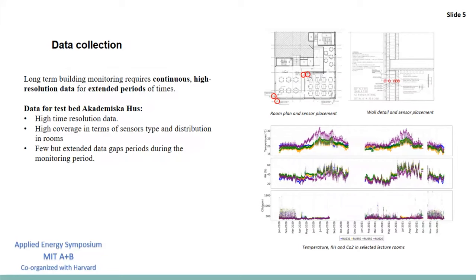Long-term building monitoring requires continuous high resolution data for extended periods of time. For this specific building the resolution of the data and coverage in terms of distribution is high. In the figure on the right hand side you can see the distribution within one of the floor plans and the construction details showing sensors embedded within the wall structure. The plot below shows hourly temperature, relative humidity and CO2 concentration during 2020 and 2021 in selected rooms. From the plots we can see that there are extended periods of time during the monitoring period where no data were recorded.